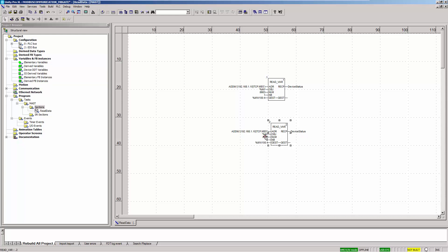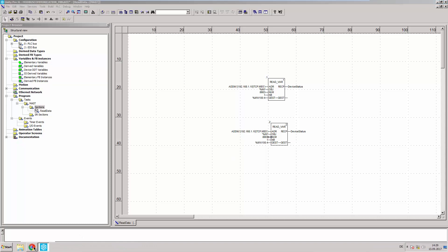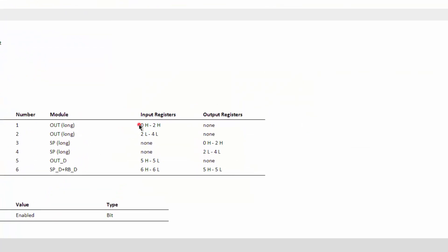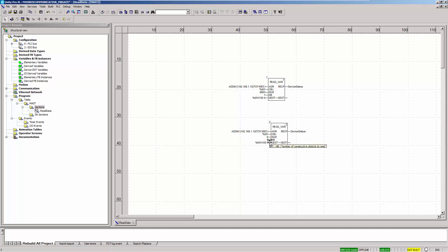Check the Modbus mapping of the input data of the first AI module in the HTML report. It can be seen that the data starts on register 0 and occupies the first two registers as well as the high byte of the third register. Adjust the start register and the number of registers to be read accordingly. Define a new management parameter and create a new array variable with the necessary length for the output parameter RECP.